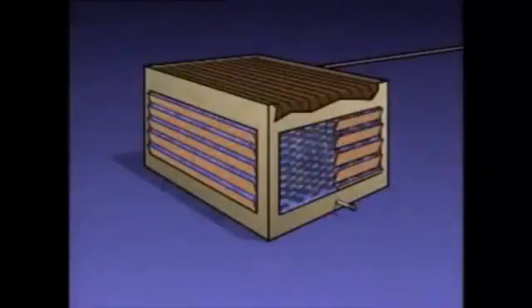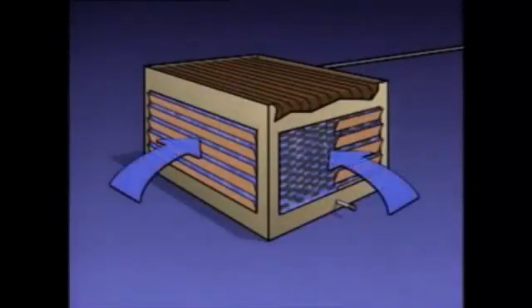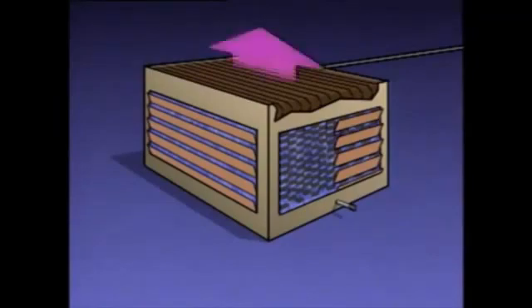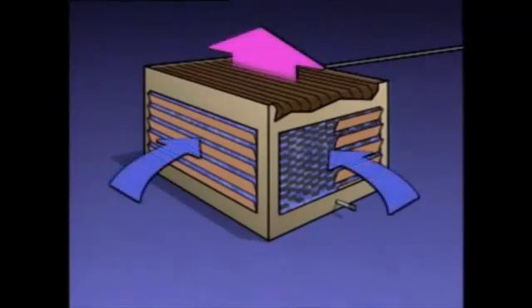Even though all cooling towers operate on the same basic principles, their designs can be divided into two broad categories: natural draft towers and mechanical draft towers. The term draft refers to the flow of air through the tower. In a natural draft cooling tower, air flows through the unit naturally without the aid of mechanical devices. As the water evaporates and heats the air, the air inside the tower becomes warmer and less dense than the surrounding air. As the less dense warm air rises up through the tower, denser, cooler outside air is drawn into the bottom of the tower.